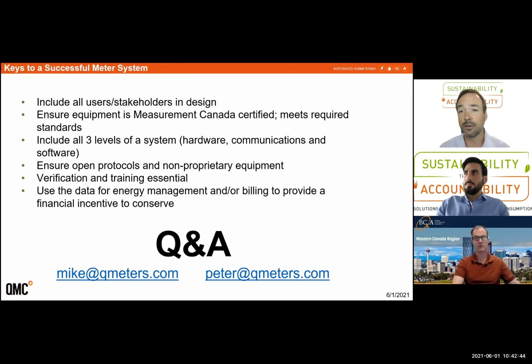Verification of the systems is critical so that you're 100% assured that the meter reads you're getting are accurate, the installation is done correctly, and verify and ensure training is done so that people who are going to utilize the system know what they're doing with the system and come back and use it regularly. And lastly, please do utilize these systems in the end for energy management or billing purposes. We've seen too many meter systems get deployed and not be used to their full potential. So they're just not getting the sustainable savings that we're looking for from these systems once deployed. So ensure that the groups who are tasked with using them are using their full potential.